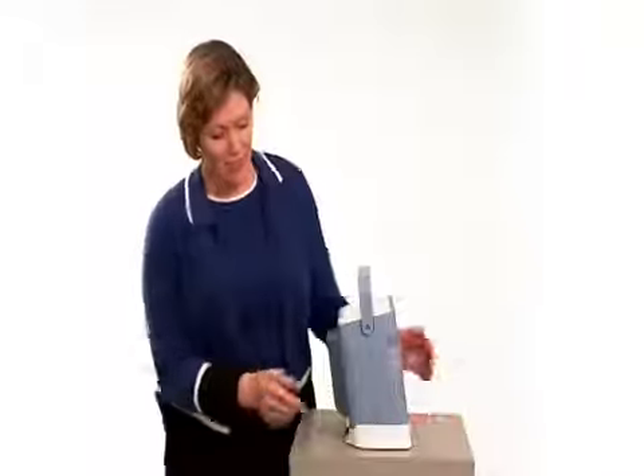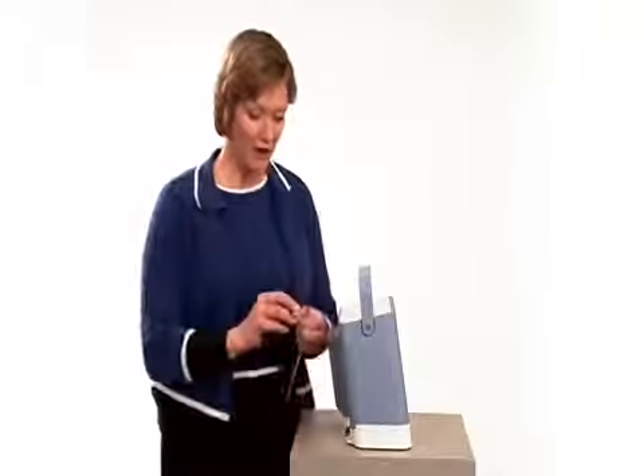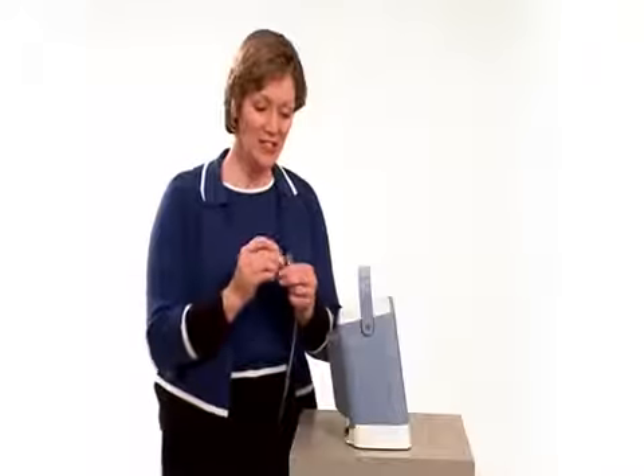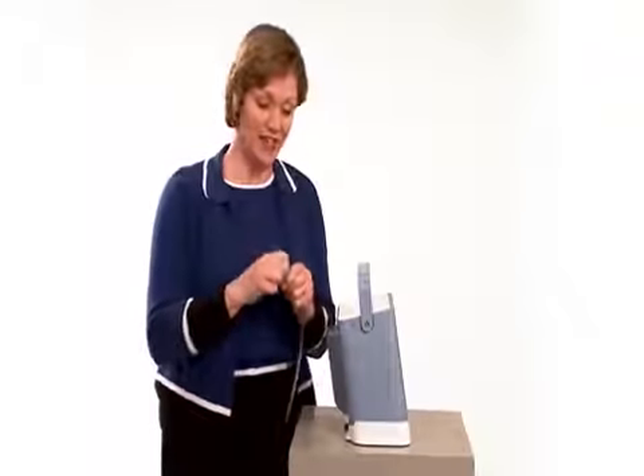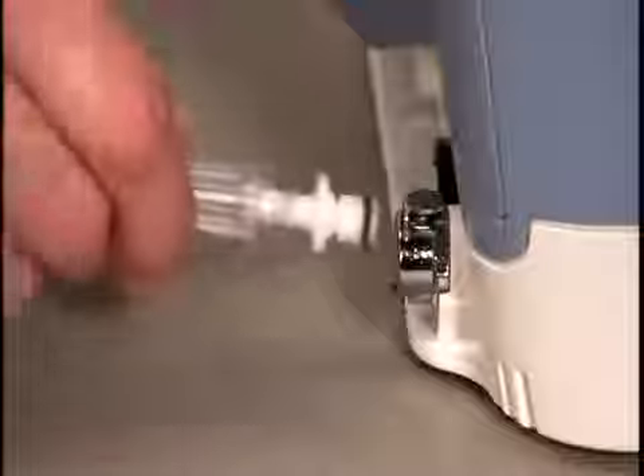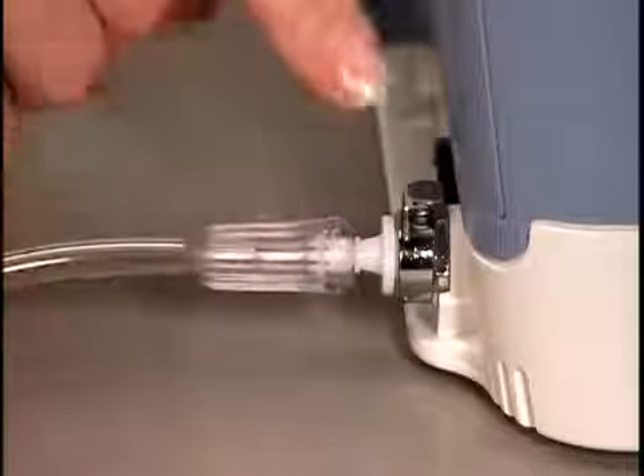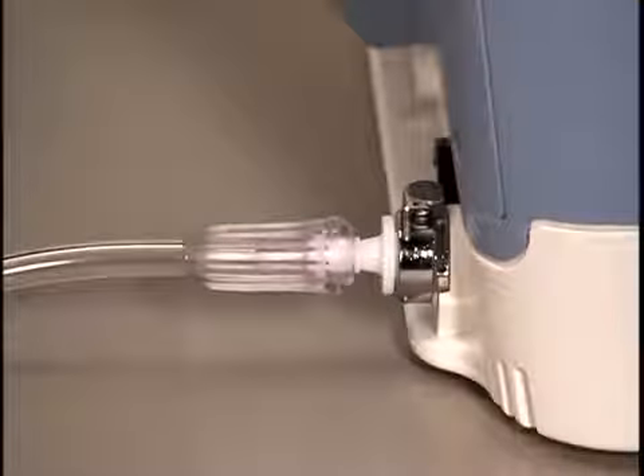If the physician has prescribed supplemental oxygen, that port is here on the back of the device. Connect the oxygen tubing to an oxygen valve quick connect. Attach the quick connect to the oxygen valve inlet on the back of the ventilator. Make sure you press the oxygen valve quick connect firmly into the inlet. You should hear a click and see the tab at the top of the port pop up. Once Trilogy 100 is set up, you're ready to turn it on and interact with the screens.